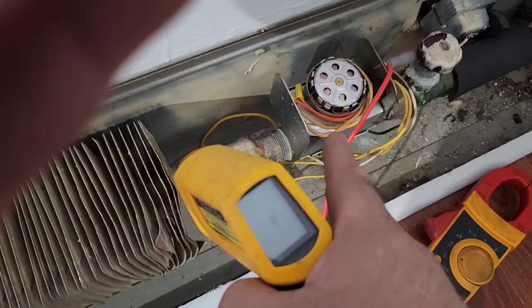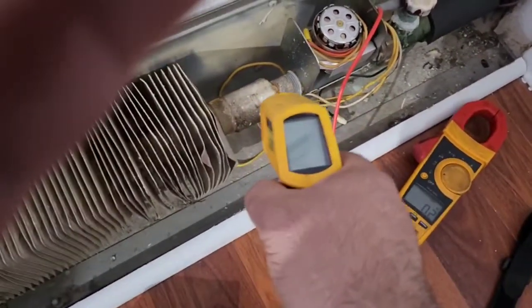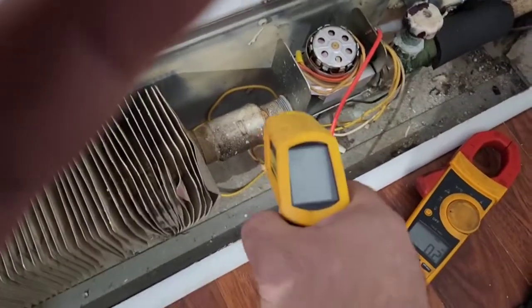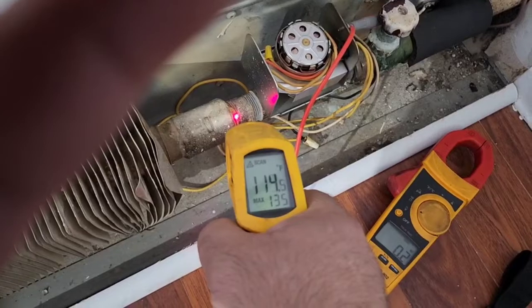If I take that jumper off, the valve is de-energized. It's a slow closing and slow opening valve. So this temperature has to go up right now — that means that valve is fully open, and you can see the temperature is going up.